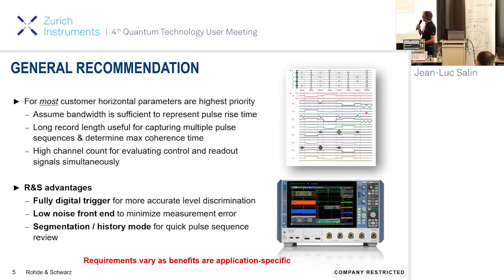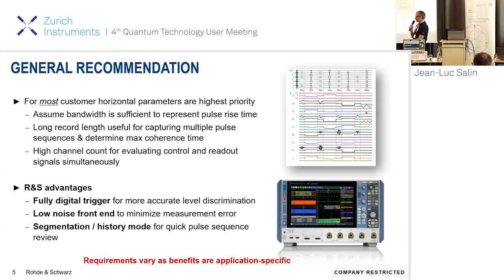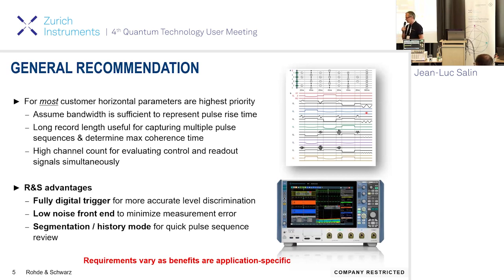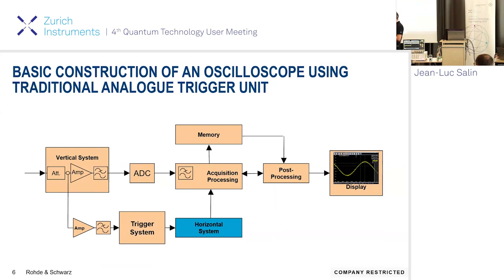The main advantages of Rohde & Schwarz oscilloscopes are: a digital trigger, a very low noise front-end because Rohde & Schwarz designs the amplifiers and ADC in-house with the goal of lowest noise on the market, and oscilloscopes with very long memories so you can store and save long sequences of pulses. I want to focus on one key point: the difference between an oscilloscope with a digital trigger versus an analog trigger.